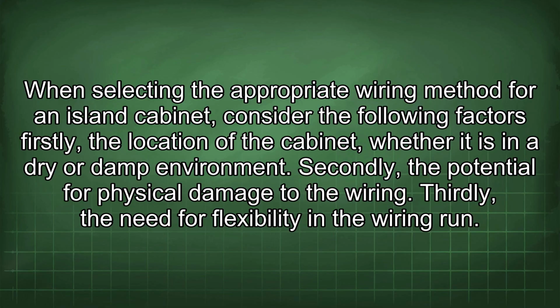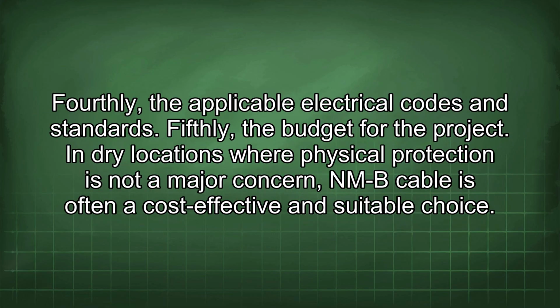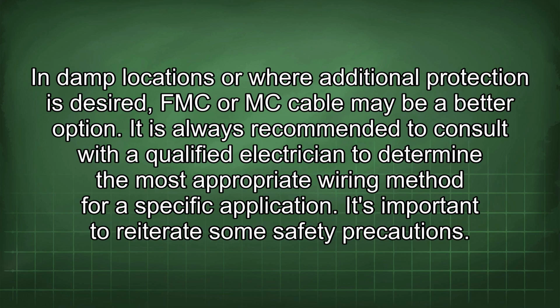Secondly, the potential for physical damage to the wiring. Thirdly, the need for flexibility in the wiring run. Fourthly, the applicable electrical codes and standards. Fifthly, the budget for the project. In dry locations where physical protection is not a major concern, an NMB cable is often a cost-effective and suitable choice. In damp locations or where additional protection is desired, FMC or MC cable may be a better option.